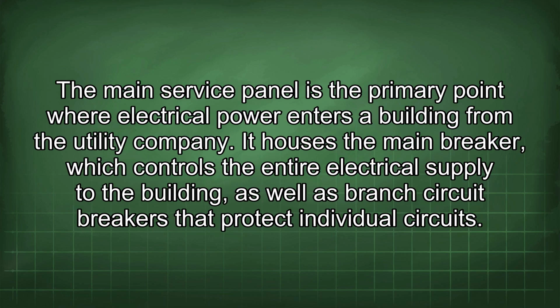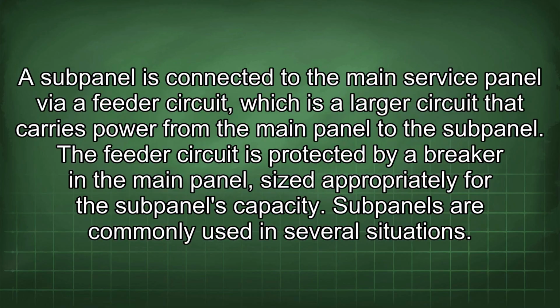The main service panel is the primary point where electrical power enters a building from the utility company. It houses the main breaker, which controls the entire electrical supply to the building, as well as branch circuit breakers that protect individual circuits. A subpanel is connected to the main service panel via a feeder circuit, which is a larger circuit that carries power from the main panel to the subpanel. The feeder circuit is protected by a breaker in the main panel, sized appropriately for the subpanel's capacity.